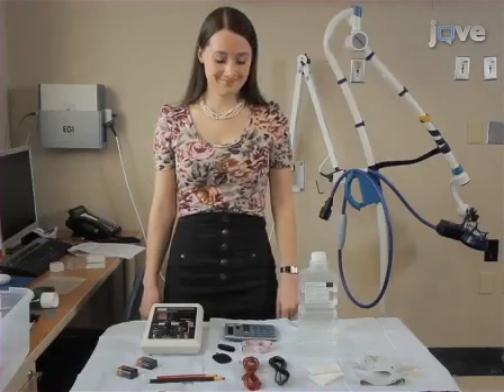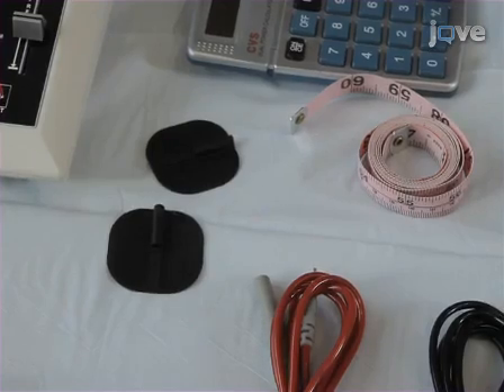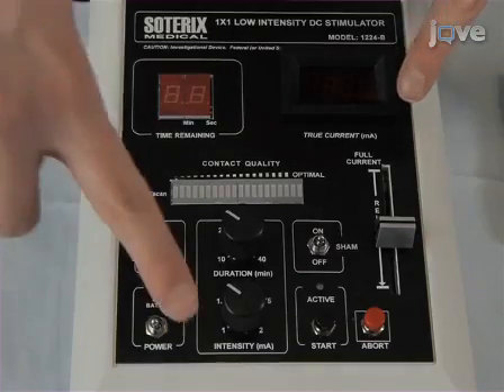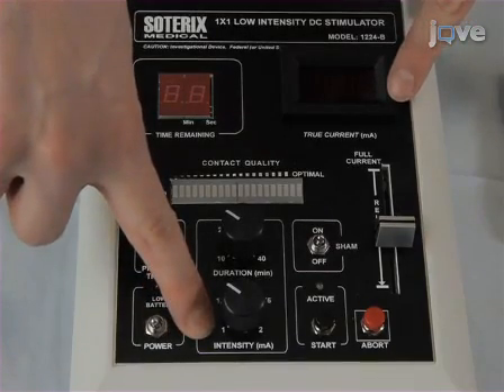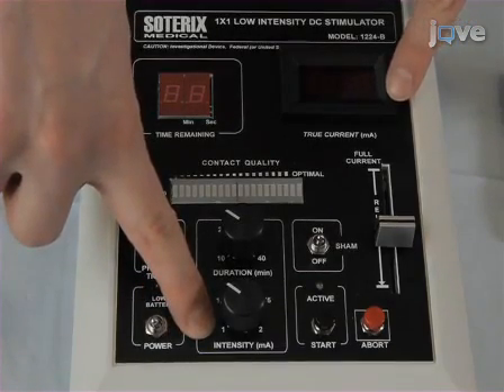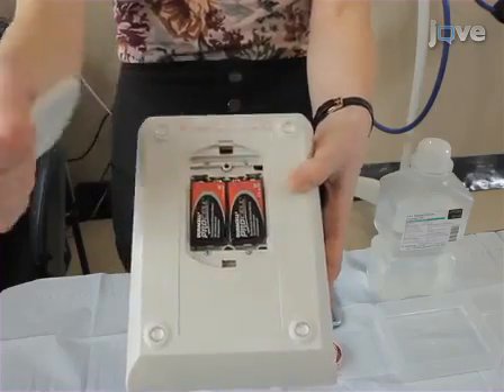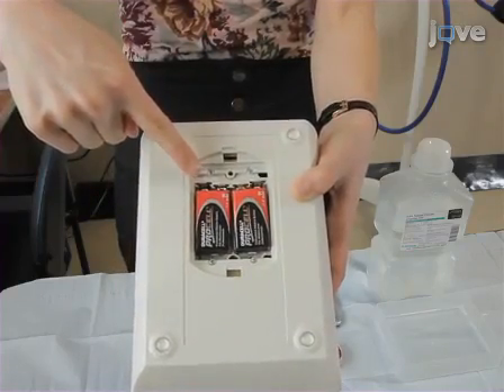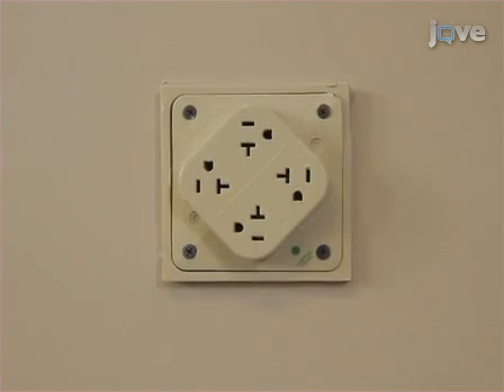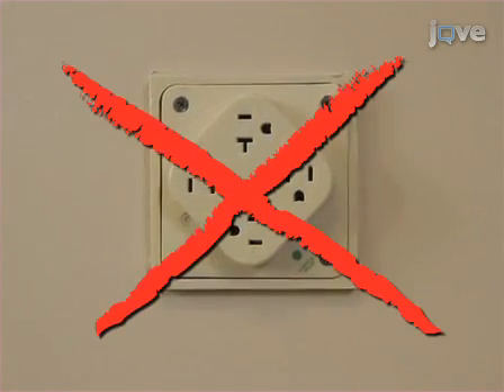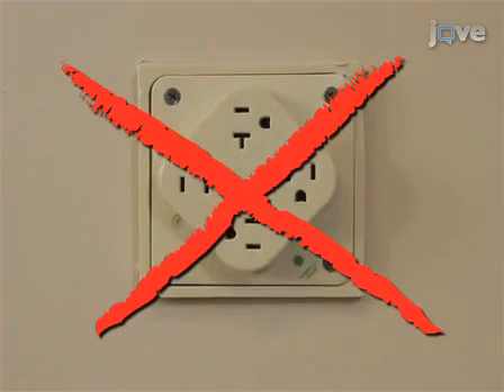Before beginning this protocol, assure that all needed materials are available. TDCS devices should be battery-driven and constant current controlled with a maximum output of a few milliamps. In some devices, the batteries can be chargeable.